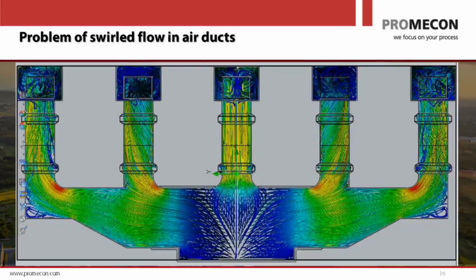Now have a look at the manifold left and right from that. You will see the air does not only have to turn upwards, but it also has to turn sideways. It has to turn left, and then left again, and upwards. So basically, what this motion describes is a sort of a screw-type movement. Now, as the air has a mass and an inertia, it does not want to follow this, so therefore it starts to screw counterclockwise. It spins. And that swirl can be easily seen in this CFD simulation. So the two manifolds left and right have a very strong spin in opposed directions. Why is this a problem? Any delta P measurement or any thermal mass flow measurement is a scalar measurement.